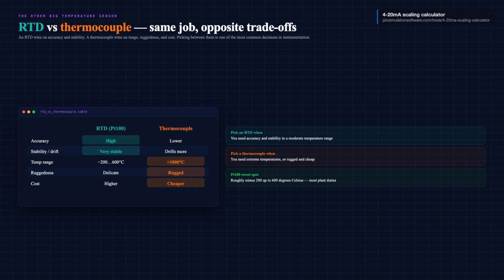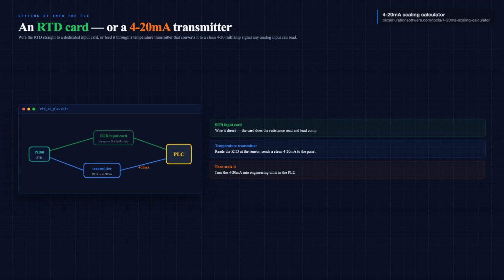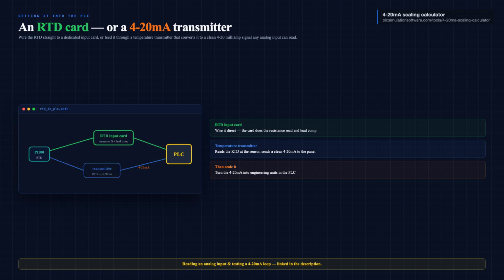Finally, how does the reading get into the PLC? Two common paths. The first is a dedicated RTD input card. You wire the RTD straight to it and tell it the type and the wiring. The card does the resistance measurement and the lead compensation for you. The second is a temperature transmitter. The transmitter sits at the sensor, reads the RTD, and converts the temperature into a clean 4 to 20 milliamp signal. Then any ordinary analog input can read it, and the long run to the panel stays immune to noise.